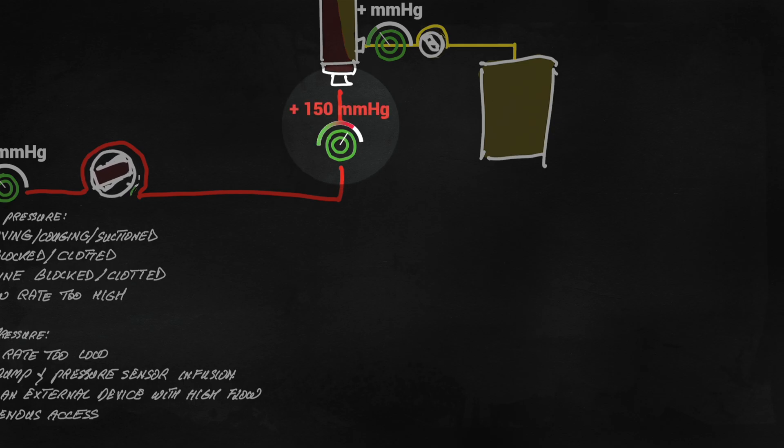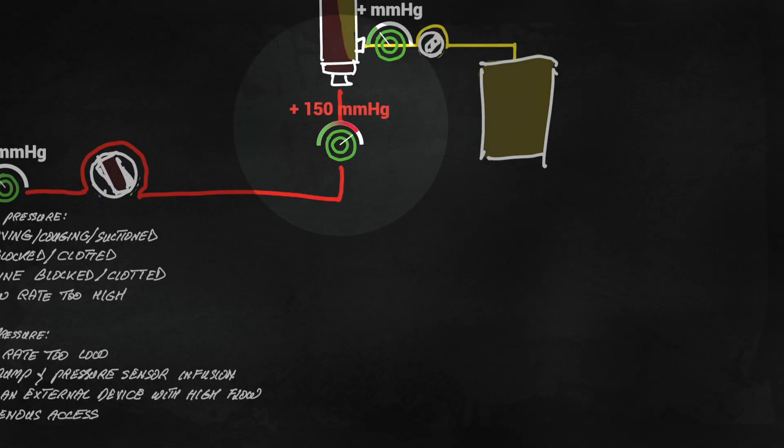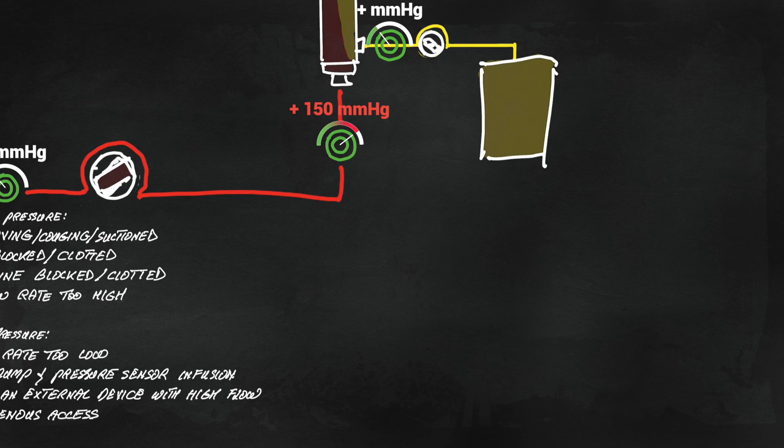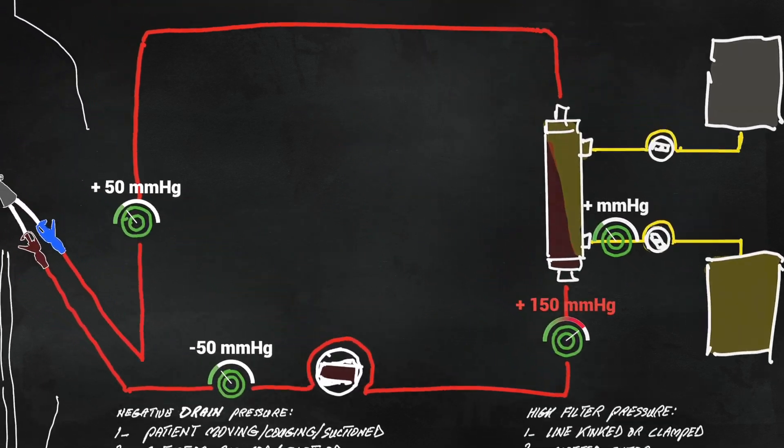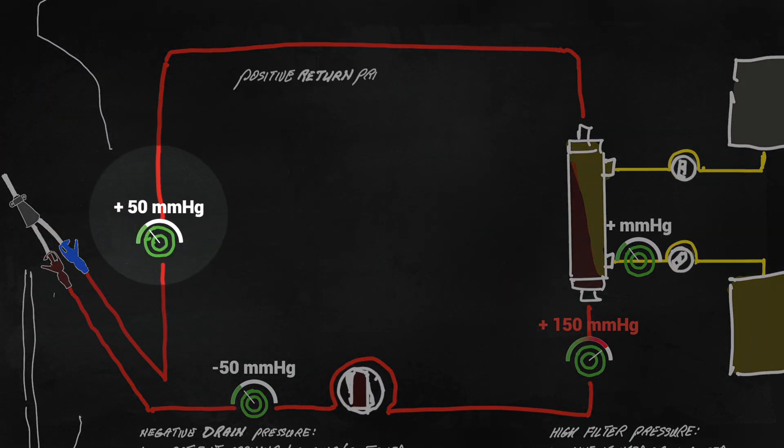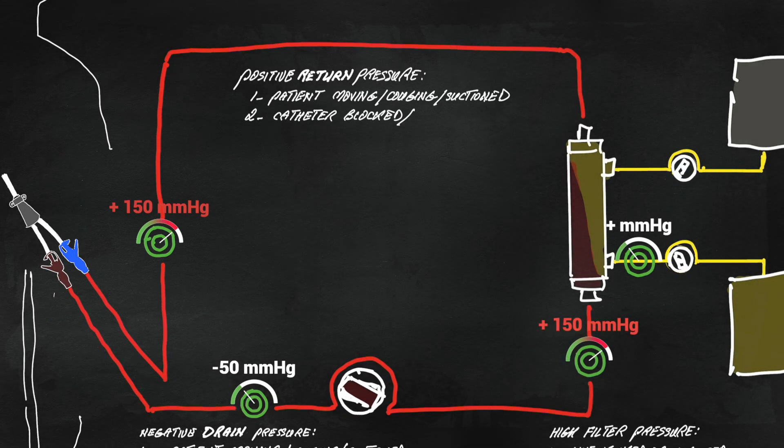The filter pressure will rise due to filter clotting or any blockade or kink in the line downstream. Similarly, the return pressure can go up when the catheter port is clotted or the return line is blocked or kinked.